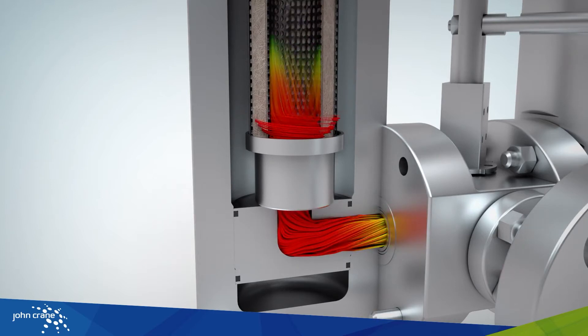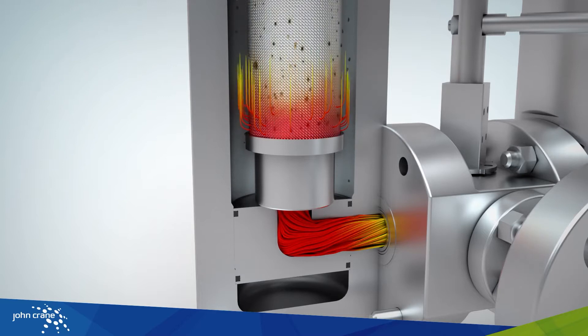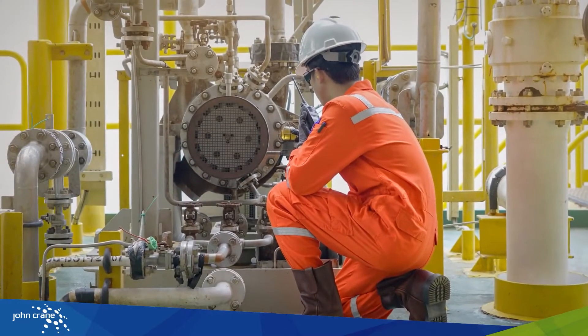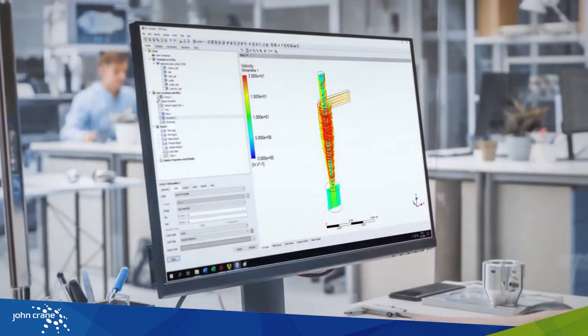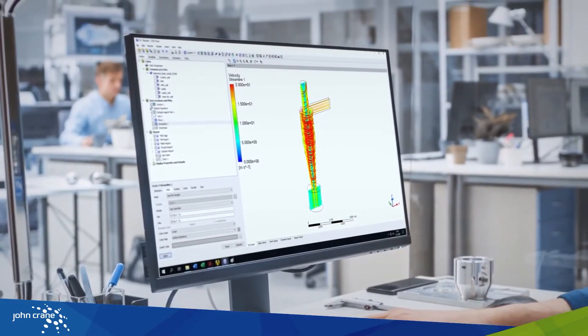The outward-directed motion of the vortex naturally increases the velocity in the wet band of the filter element, increasing the likelihood of droplet re-entrainment and reducing efficiency. The result is that the dry gas seal is not optimally protected and a relatively high system pressure drop is seen. Such inefficiencies are the cause of unplanned downtime, more maintenance, and increased OPEX. Using computational fluid dynamics, a more efficient solution has been developed.